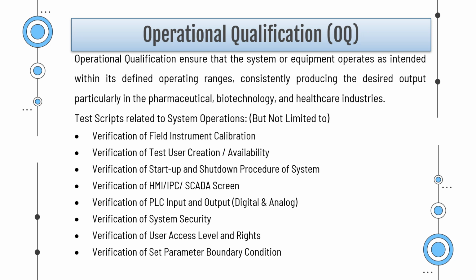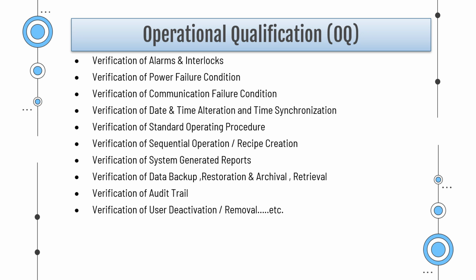Verification of set parameter boundary condition. Verification of alarms and interlocks. Verification of power failure condition. Verification of communication failure condition. Verification of date and time alteration and time synchronization. Verification of standard operating procedure.